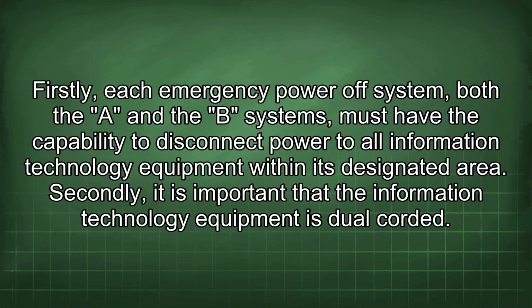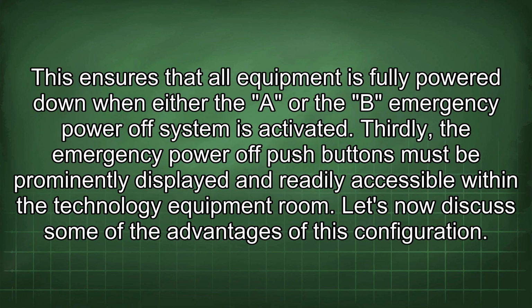Firstly, each emergency power-off system, both the A and the B systems, must have the capability to disconnect power to all information technology equipment within its designated area. Secondly, it is important that the information technology equipment is dual-corded. This ensures that all equipment is fully powered down when either the A or the B emergency power-off system is activated. Thirdly, the emergency power-off push buttons must be prominently displayed and readily accessible within the technology equipment room.